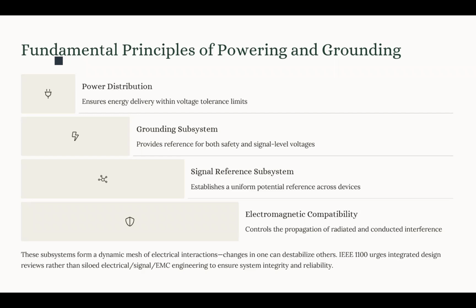When we talk about the power distribution subsystem, this subsystem is responsible for delivering the electrical energy to the equipment within acceptable voltage, current, and frequency tolerance. The requirements mentioned in IEEE 1100 include voltage stability, where we maintain the nominal voltage under full load condition within plus or minus 5%, and waveform integrity, which means total harmonic distortion, THD, should be less than 5%.